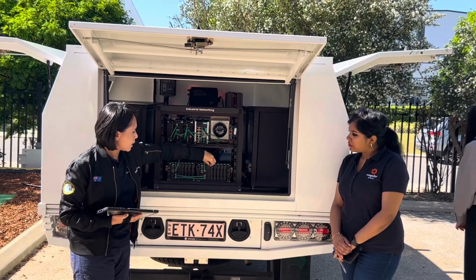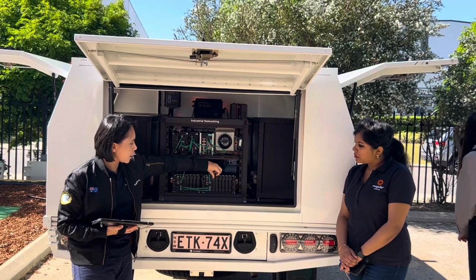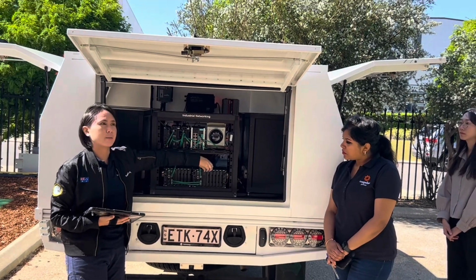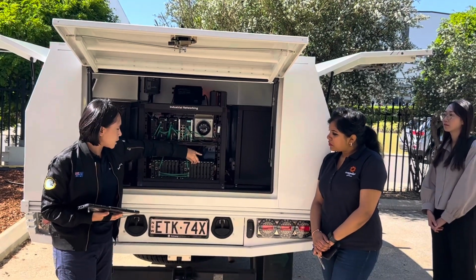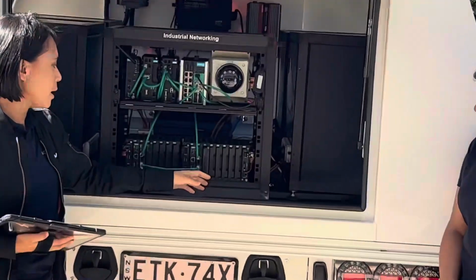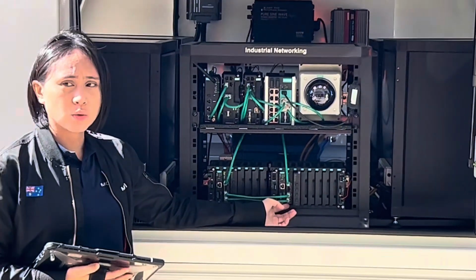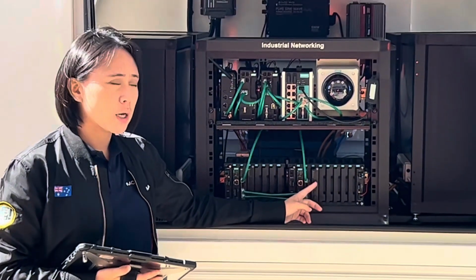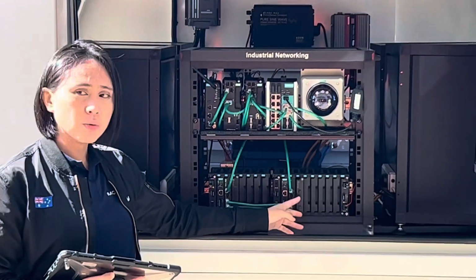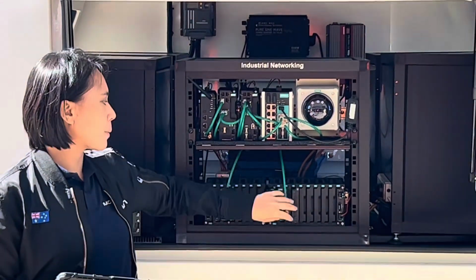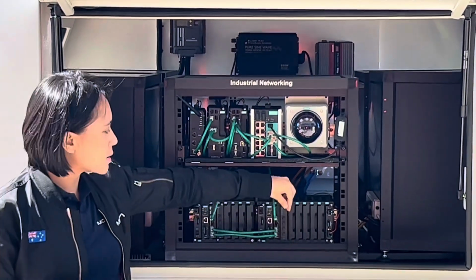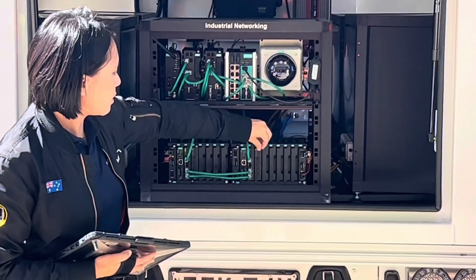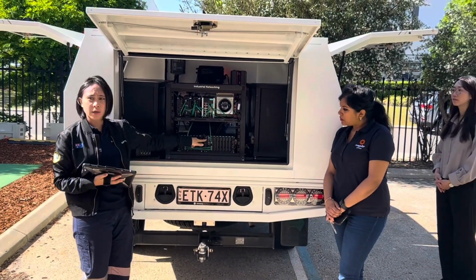Each of them is a 4-port module, and those modules are designed to be hot swappable. That is a very preferred function for an OT environment, because we don't want to shut down the switch when an issue happens to just one slot of your module or one of your ports. You only need to replace one module. You don't need to replace all the switches. When you replace it, you just buy a new one, slide in the new one and screw it up again. It's already up and running.